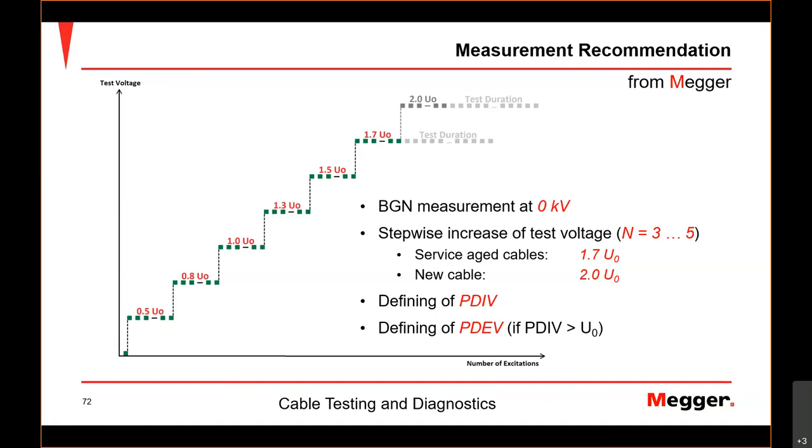And if a contractor does the joints, you can say, hey, 1.7, and we did find a little bit of partial discharge. Well, the contractor might say, well, but that's only very little, that's not so important. Well, will you accept it or not?